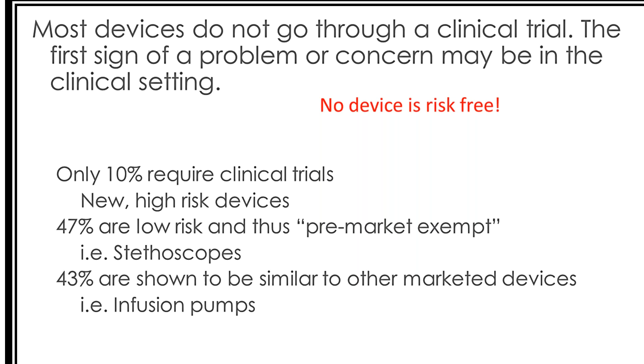And 47% of them are really low-risk devices, so they are exempt from pre-market review. For example, a class 1 device such as a stethoscope, or in the case of surgical instruments, surgical retractor kits. There are hundreds of different product codes that are exempt. They only have to register. And another 43% are shown to be similar to other devices on the market. For example, if you have an electric biopsy forceps that somebody made 30 years ago, you can get a 510(k) clearance and utilize that as a predicate device.